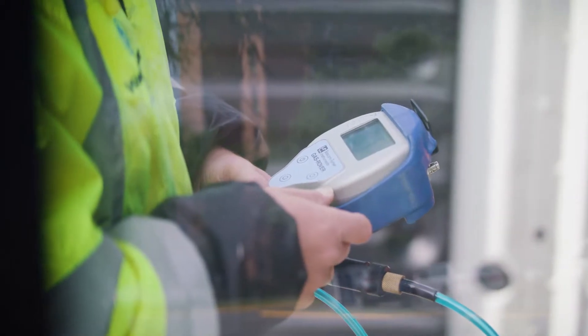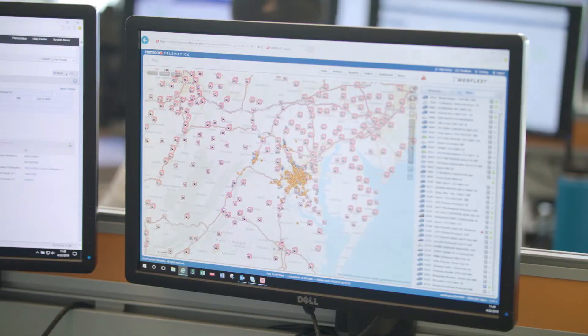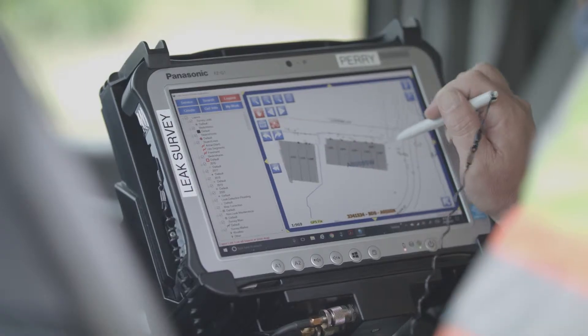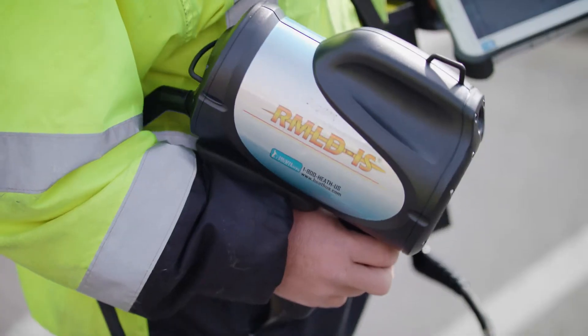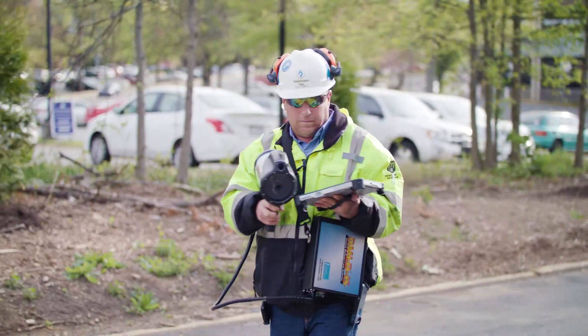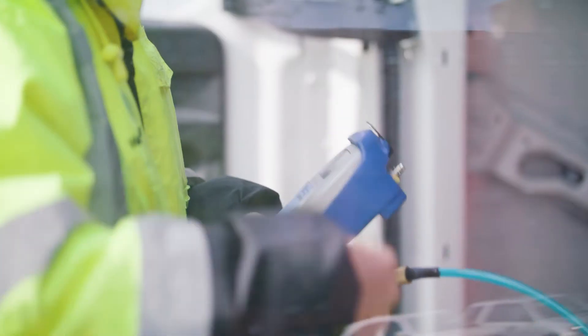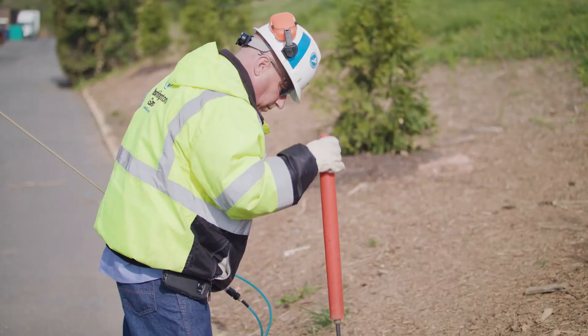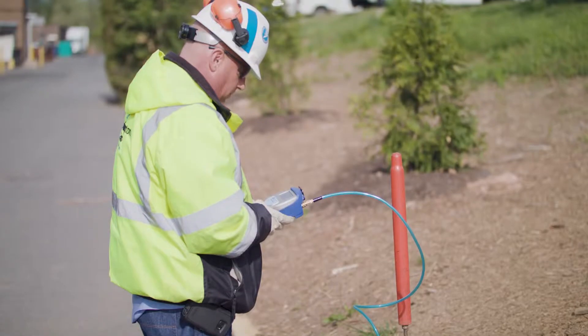The inspection itself includes the following steps. We maintain detailed maps that provide the specific location of our gas pipes on the property of both businesses and residents. Our handheld meters and diagnostic tools use laser imaging to detect levels of methane in the air. If we find a leak, we use the proper equipment and process to identify the exact location and assess the leak.